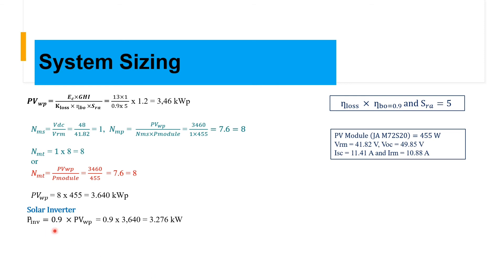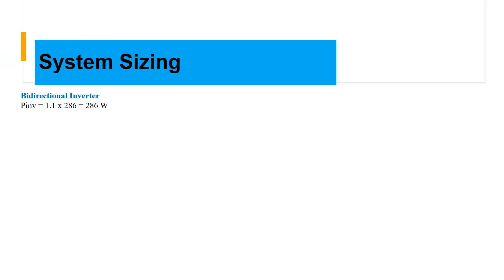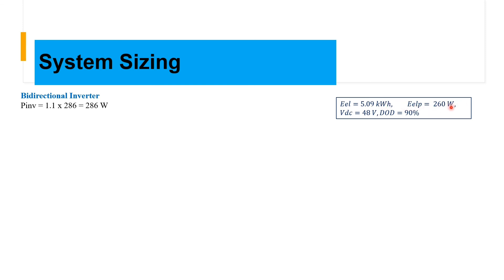Now we can size our solar inverter. The solar inverter is sized at 0.9 times the PV array, which gives us 3.276 kilowatts — within the recommended inverter sizing ratio of 0.9 to 1.2. Now let's size our bidirectional inverter, which is sized at 1.1 times 260 watts — the power of the essential loads — giving us an inverter size of 286 watts.